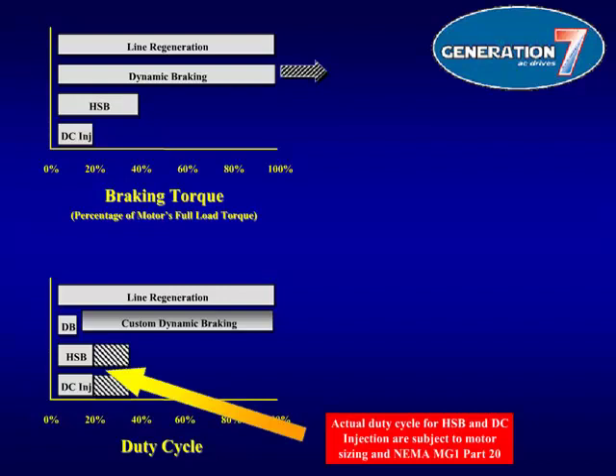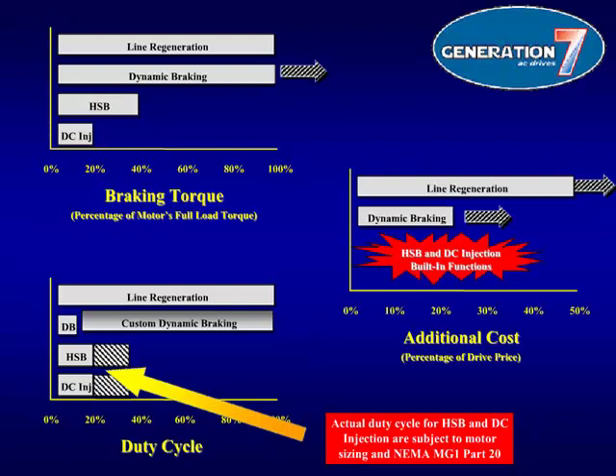High-slip braking and DC injection duty cycles vary depending on parameter settings and motor sizing, and are subject to meeting the NEMA MG1 Part 20 standards. Looking at additional cost, although high-slip braking and DC injection may not offer the same braking torque or duty cycle as line regeneration or dynamic braking, they are built into the drive and require no additional cost. Dynamic braking can cost up to 25% of the drive's price, whereas line regeneration can cost up to 50% of the drive's price. Comparing the application to these criteria enables the correct braking method to be determined.